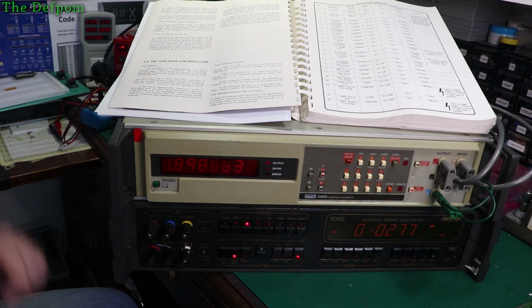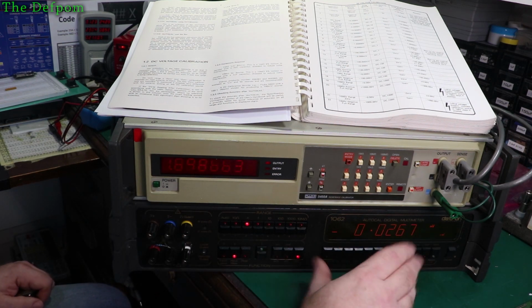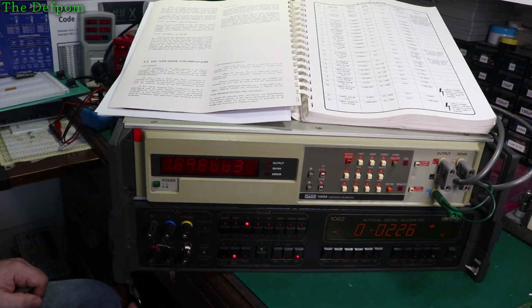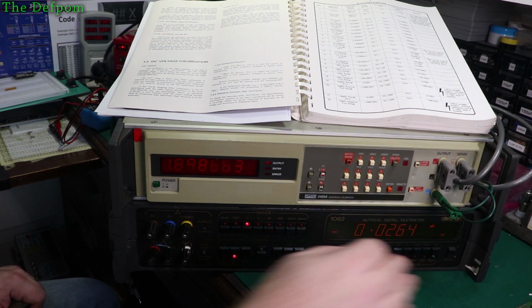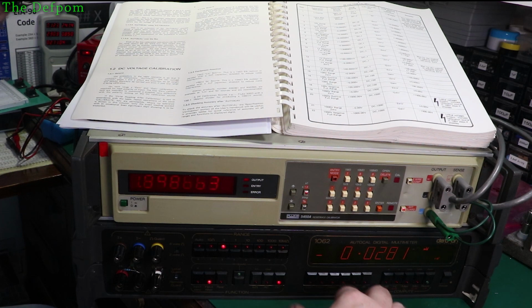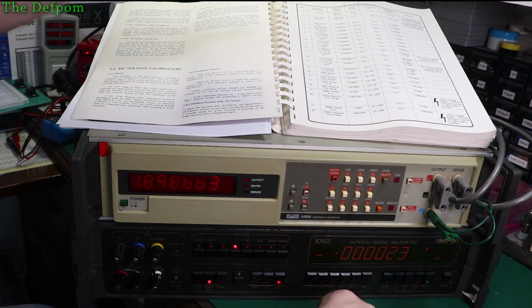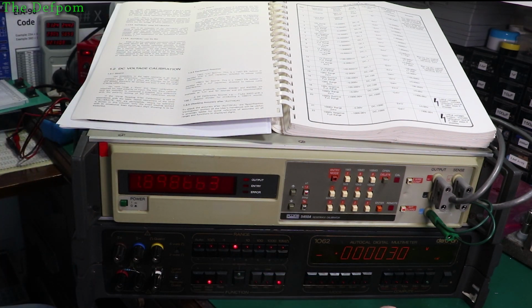The idea of this particular stage is to do a linearity adjustment. I'm still in calibration mode, nothing's changed there, but I'm in DC, nothing's connected across the front, nothing shunt, so I've got it on 2-wire in case it matters, local guard still. It should be on DC, 1 volt range, filter on, which is what I'm in, and then I should be getting less than 10 counts, but I'm getting more than that. So I need to redo this linearity.